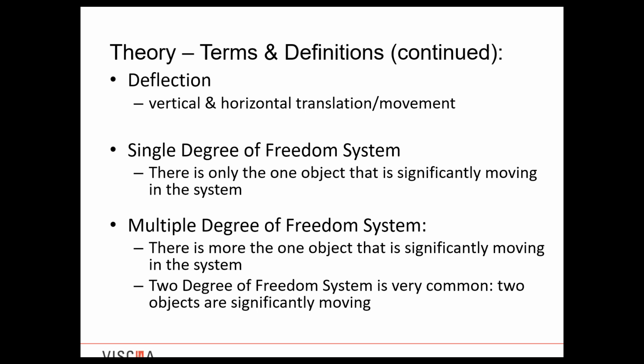So when we talk about deflection, and John was talking about earlier how in our industry we talk about revolutions per minute or inches of deflection. When we talk about deflection, you can have vertical or horizontal deflection. But again, it's that translation, it's that movement that's deflecting. And typically when we're talking about equipment, usually it's a vertical deflection. If we get into concerns regarding wind and seismic on that equipment, then we have to consider horizontal translation or deflection. So the next two concepts are basic, but then they start to build kind of like building blocks when you're learning new concepts. And later on, I have some slides that visually show this, and I might try to advance to those slides so that you can have a visual aid here.